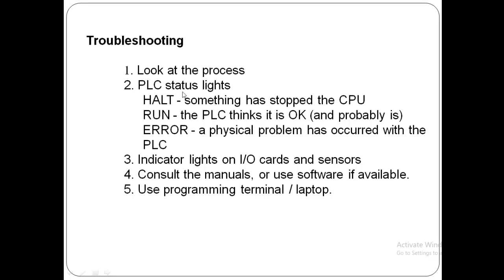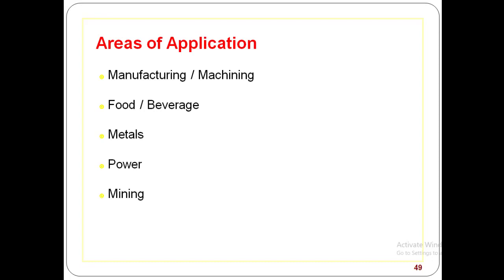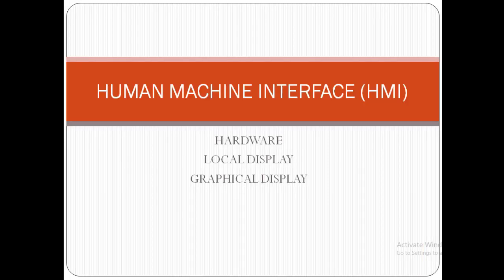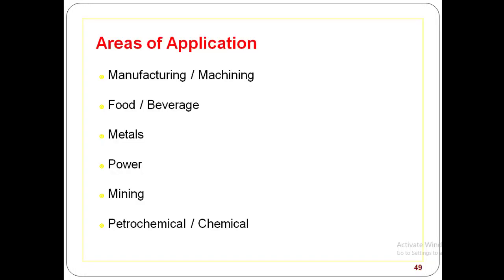Troubleshooting a PLC is straightforward if you follow these steps: look at the process status lights — check whether the halt light is on or off, check the run light to see if it is okay, and check the error light, which will be on if there is an error. Check indicator lights on the input/output cards to see which inputs or outputs are active. Consult the manuals, use software if available, and use a programming terminal or laptop to check. Key application areas include manufacturing, machining, food and beverage, metals, power industries, mining, petrochemical, and chemical industries.